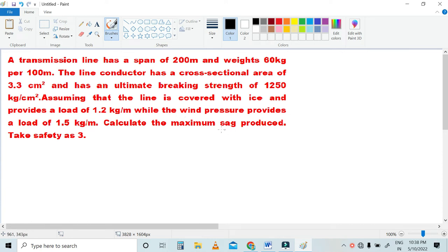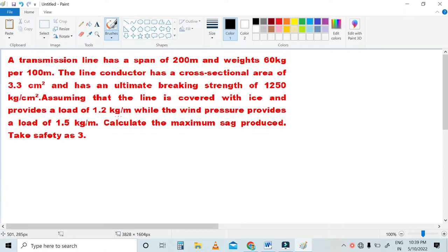In this video, we start calculation based on the following problem. A transmission line has a span of 200 meters and weighs 60 kg per 100 meters. The line conductor has a cross-sectional area of 3.3 cm² and has an ultimate breaking strength of 1250 kg per cm². The line is covered with ice providing a load of 1.2 kg per meter, while wind pressure provides a load of 1.5 kg per meter. Calculate the maximum sag produced. Take safety factor as 3.